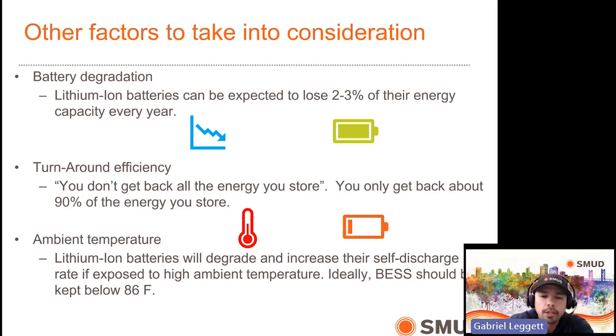We mentioned turnaround efficiency, so you don't get back all the energy that you stored. The other thing to take into consideration is ambient temperature. Battery systems, lithium ion primarily, like to be between 50 and 86 degrees Fahrenheit. That's where they're most comfortable, without an increase in self-discharge or degradation.